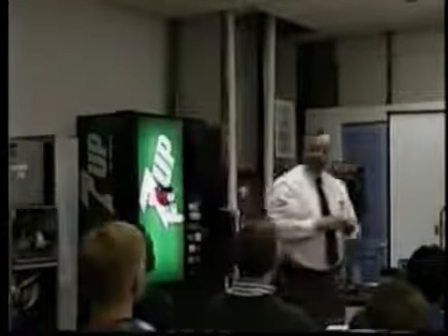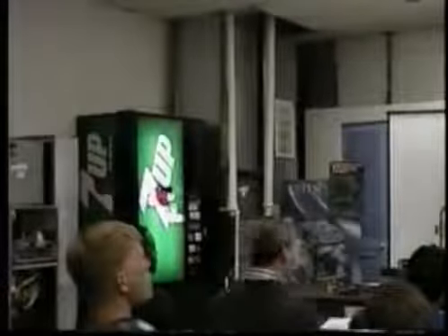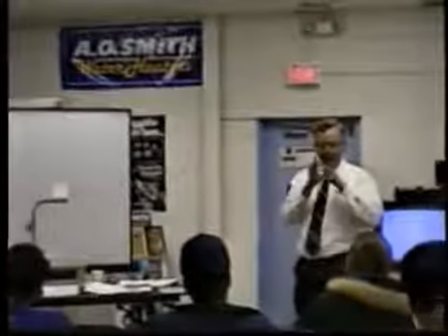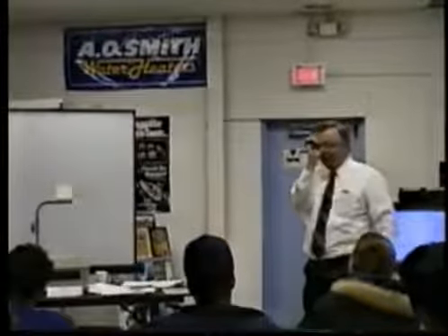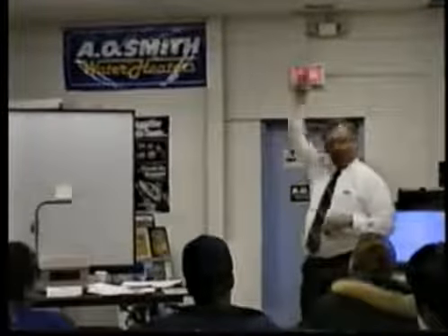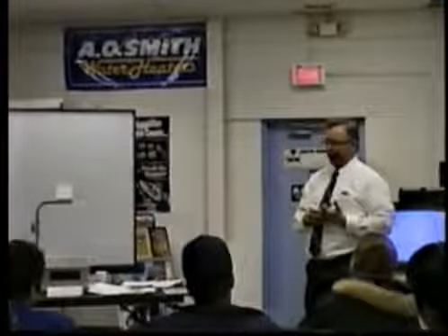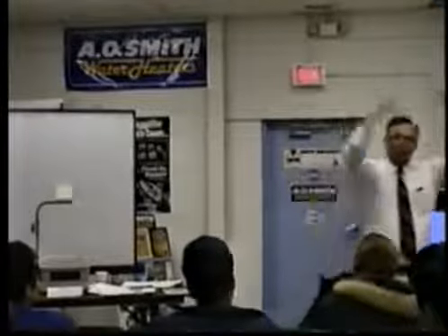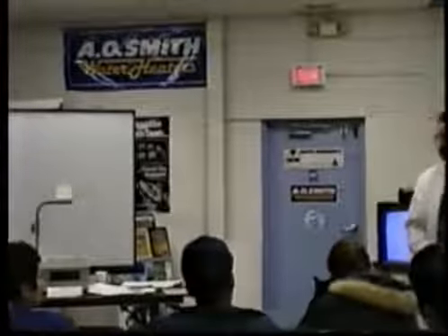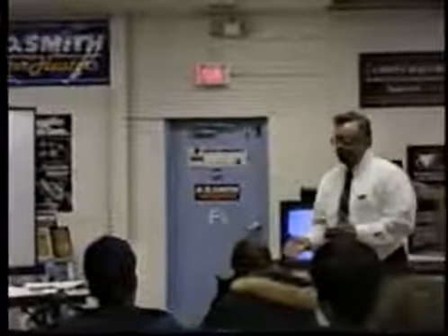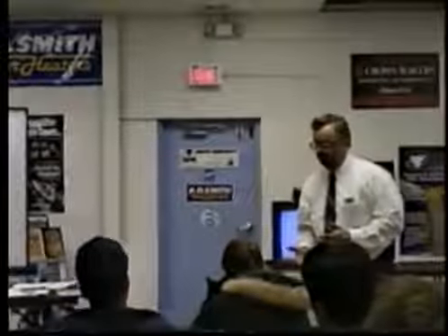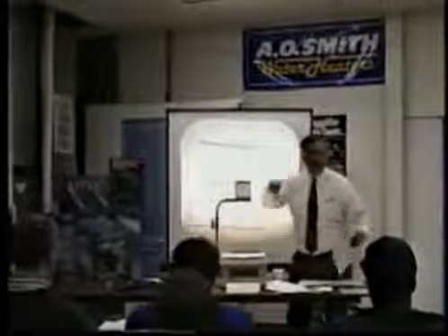We're going to be talking about atmospheric pressure later. Atmospheric pressure can push a column of water like 3.5 stories high. It doesn't make any difference what the diameter of the column is. It could be that big, or it could be a big barrel 3.5 stories high, and it'll push it that high. So we can't make an instrument out of that, so we use mercury. And so now the instrument is 13.5 times smaller. It's still called inches of water, but we can also call it inches of mercury. I'm only showing you this because when we start using instruments in this business, you got to know why we use mercury and why we use water.